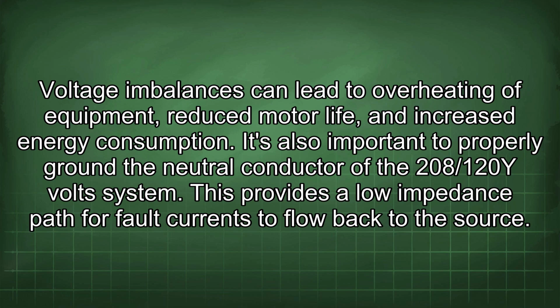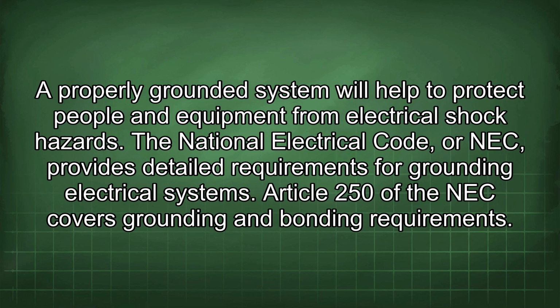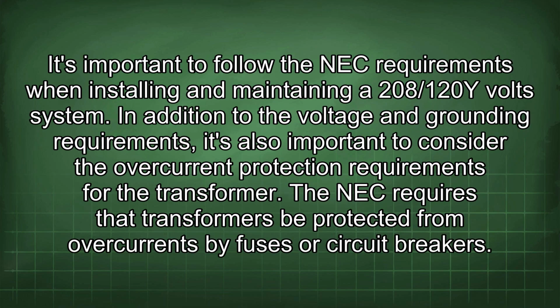It's also important to properly ground the neutral conductor of the 208/120 volt system. This provides a low impedance path for fault currents to flow back to the source. A properly grounded system will help to protect people and equipment from electrical shock hazards. The National Electrical Code, or NEC, provides detailed requirements for grounding electrical systems. Article 250 of the NEC covers grounding and bonding requirements.